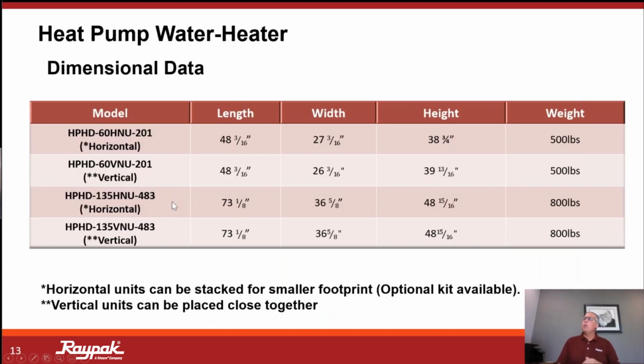So here are the models for the unit, the dimensional data. We can start out with footprint, but I'll come back to service clearances at the end. But you can see that these are very modestly sized, I would guess you would say. These can be placed indoor. They're rated for outdoor use as well. Since the higher the ambient air temperature, the higher the efficiency and the more heat we'll be able to extract from it. And we'll get into that a little bit more deeply as it pertains to the air temperatures in this presentation.